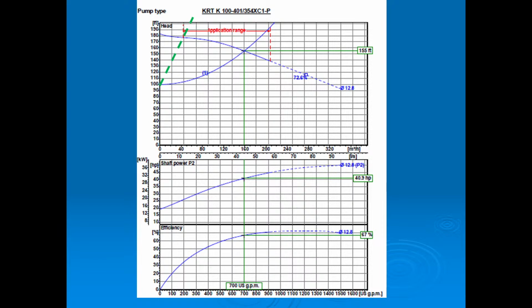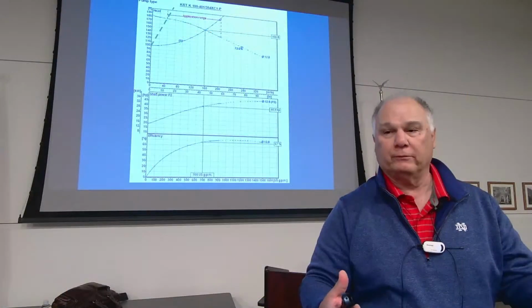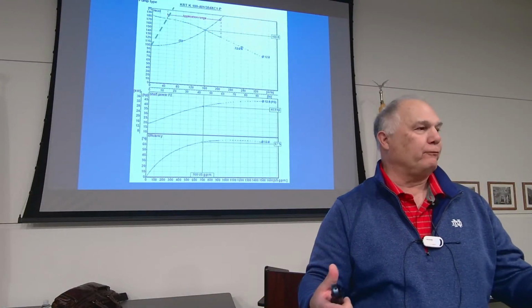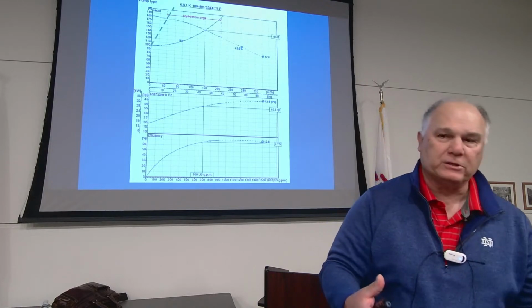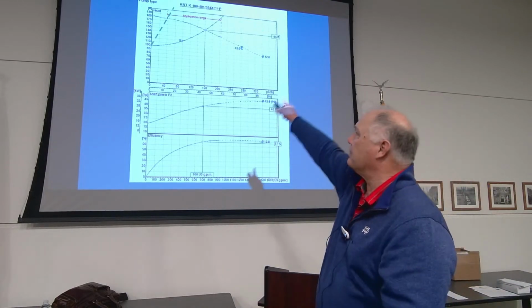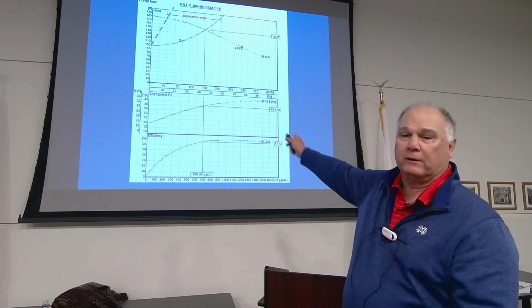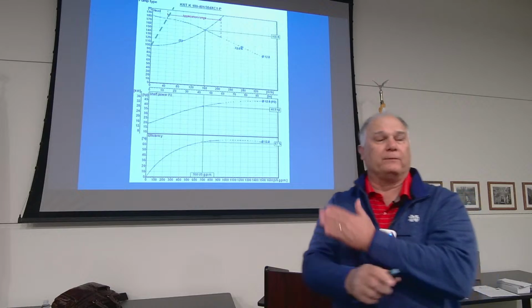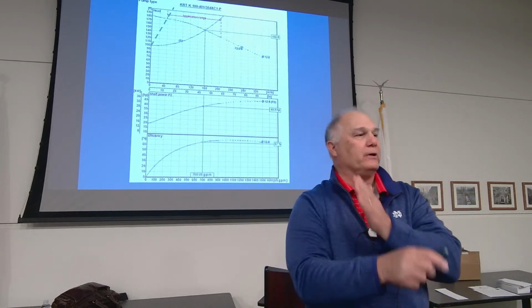What's the blue line coming down from the upper left, where it says 182, down to the very bottom right? What's that? That curve is the impeller curve. For any pump, any impeller is going to have a specific performance, regardless of where you put it. Therefore, where the system curve, which goes up to the right, and the pump curve, which goes down to the right, cross, that's going to be the exact duty condition where that pump is going to operate.